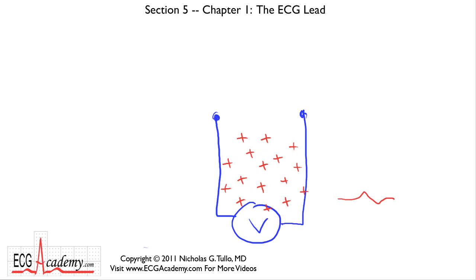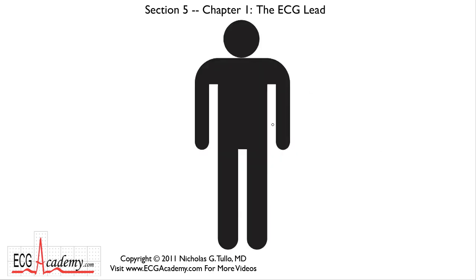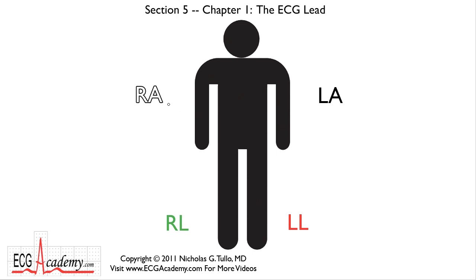When looking at the electrocardiogram coming off of an ECG system, remember we have different color codes: black is the left arm, white is the right arm, green is the right leg, and red is the left leg. In the early days of electrocardiography, they used the bipolar recording system to look at the electrical signal traveling between the right arm and the left arm.